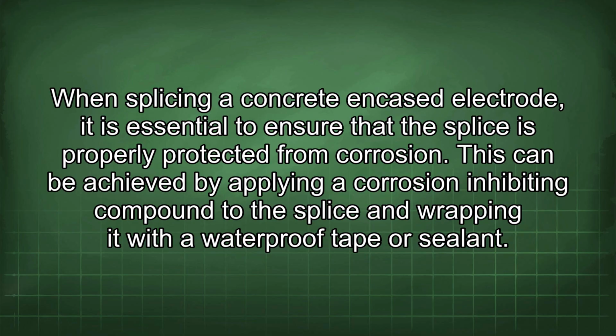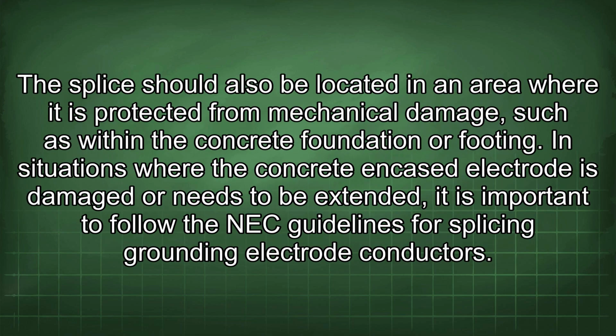This can be achieved by applying a corrosion-inhibiting compound to the splice and wrapping it with a waterproof tape or sealant. The splice should also be located in an area where it is protected from mechanical damage, such as within the concrete foundation or footing.